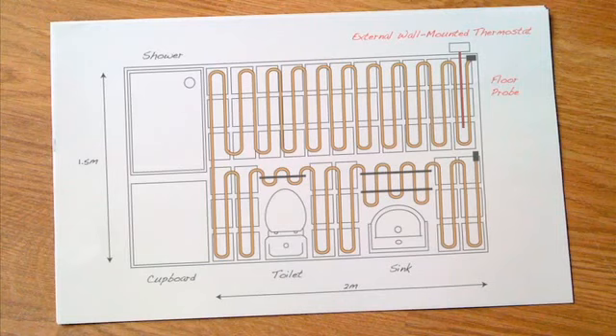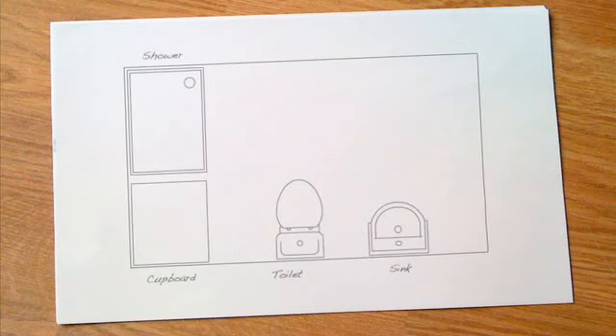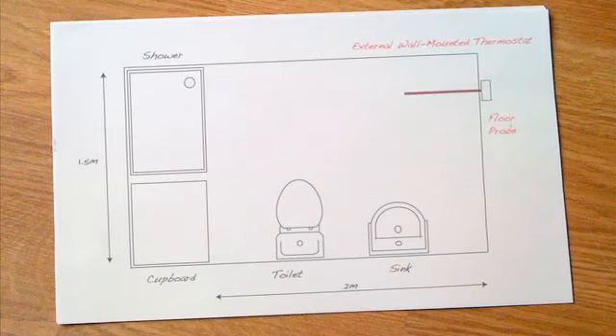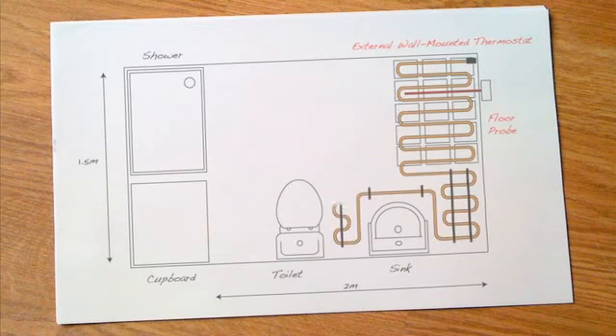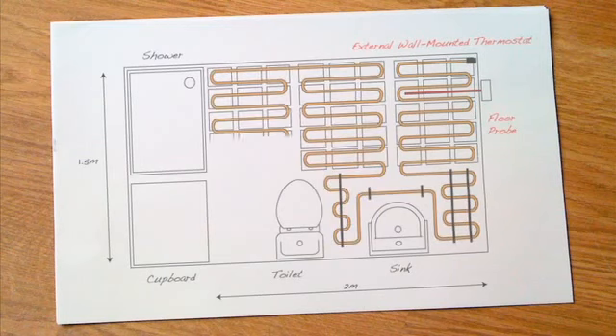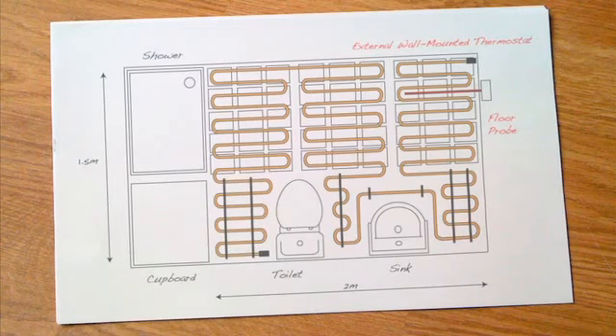We recommend that you spend time planning the installation and accurately calculate the free area of the floor that you want heated. This calculated area should then be used to select the correct cable mat size. For perimeter clearance, reduce floor area previously calculated by 10% before selecting the cable mat size. Remember to subtract any areas covered with floor-fitted furniture. It is important to select the correct cable mat size as the cable cannot be shortened.